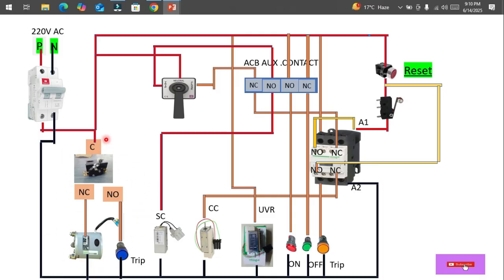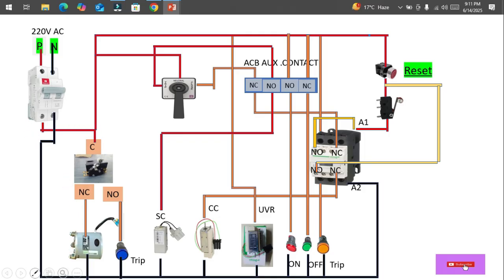Now let's come to the phase side — specifically the spring charge motor section, how the spring is charged through this motor. From the output of the breaker, the phase is going to the common point of the micro switch or limit switch. From the NC contact of the micro switch it is going to the universal motor, which is actually coupled with the spring.